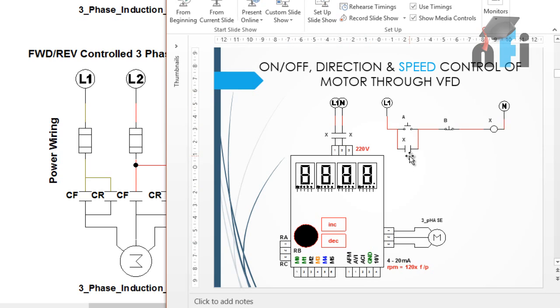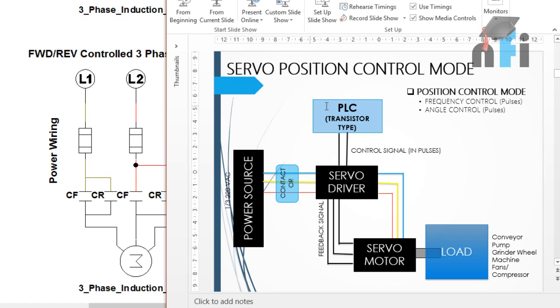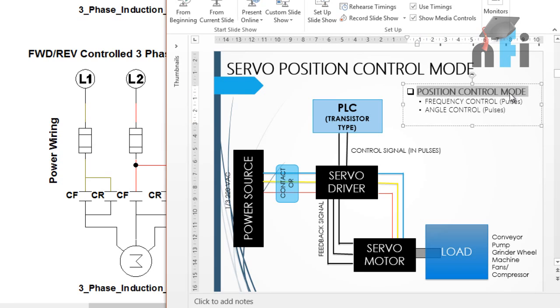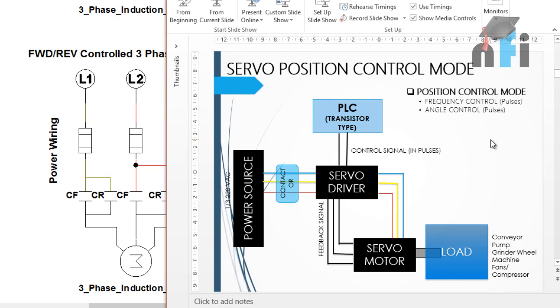There are some parameters and applications where VFD cannot be used - those applications require a servo motor. In a servo motor, the main factor is position control. We can control the position of the drive, the motor, and the load using a servo motor. In position control mode, two things can be controlled very accurately: frequency and angle (position). These two are controlled by pulses. In VFD we can control speed but not position; in servo we can control both.